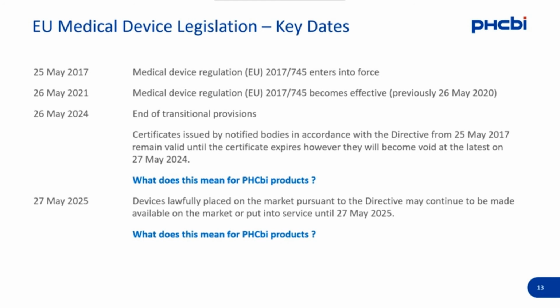They are not delayed, so they stay the same. And what it means is that certificates issued by notified bodies under the directive after the 25th of May 2017 will remain valid until that certificate expires. However, they will become void at the latest on the 27th of May 2024.